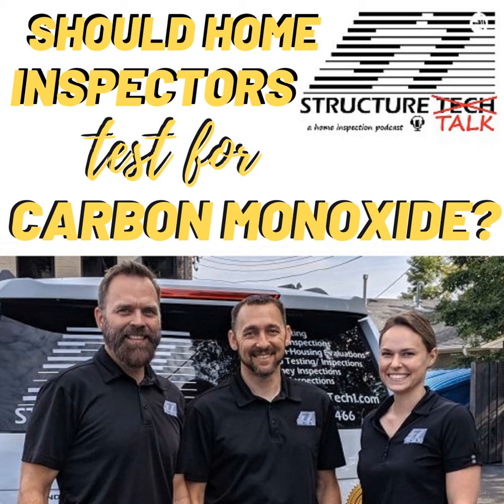Interesting. Oh, one thing I forgot to mention too is we don't drill through double wall B vents either. We only drill through single wall flues. Yep. And most of the time we don't even drill through those because there's almost always a test port there where somebody has already done it and they've covered it up with metal tape. We bring metal tape along with us, and after we make a hole, we put the same metal tape right back over the opening.